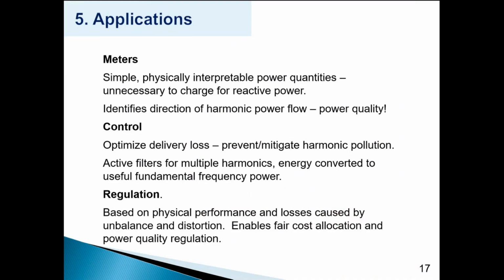Right, so what are the applications of the general power theory? Obviously, to meters. It's necessary to meter physically interpretable power quantities. So we can't measure reactive power, because the definition of reactive power is not physical. And therefore, if it's not physical, we really shouldn't be charging for reactive power. So we can identify measuring power and energy and the direction of harmonic power flow, which has all sorts of implications for those studying power quality.